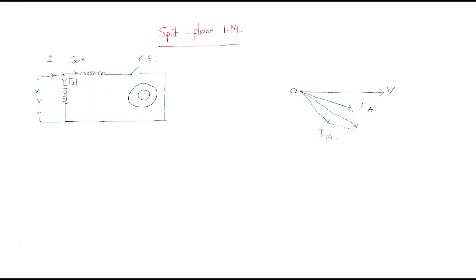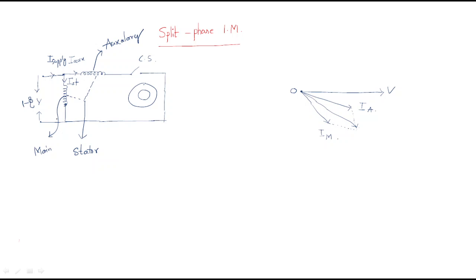Now we discuss the split phase induction motor. We have a single phase supply with supply current, and the stator windings are split into two parts. One winding is called the main winding and the other is called the auxiliary winding. Using both main and auxiliary windings together, the motor can be started.